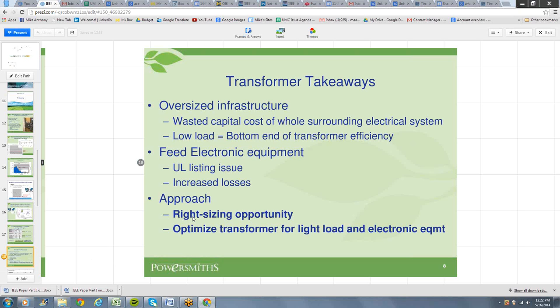So to summarize the two, there's a big right-sizing opportunity as we go in to retrofit these transformers, or even from a new construction perspective: make sure you size a transformer absolutely as tight to the load as you can, because otherwise you're going to have this drastic oversizing. The second thing you want to do is make sure that transformer is optimized for what we see, so light loading and an electronic equipment load profile. So there's the transformer in a nutshell.